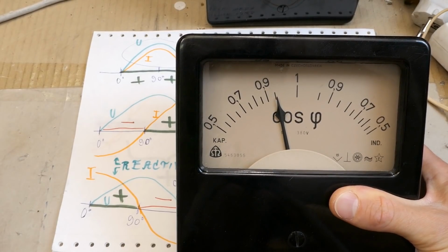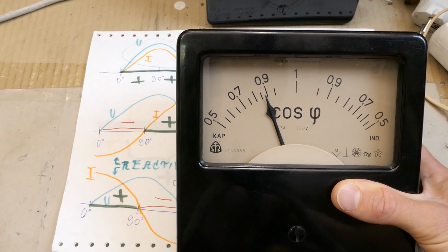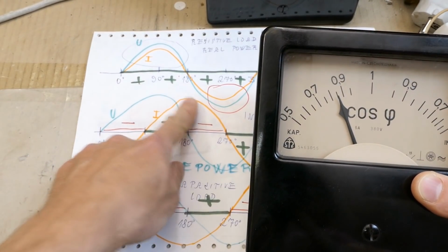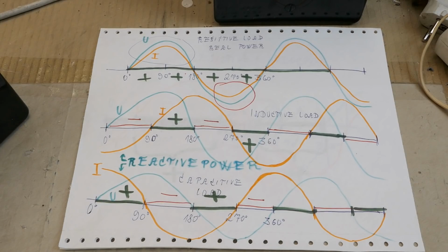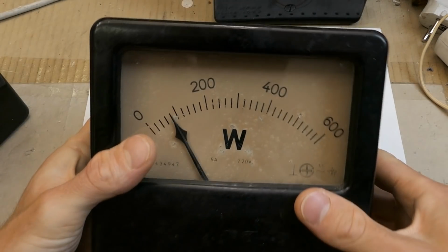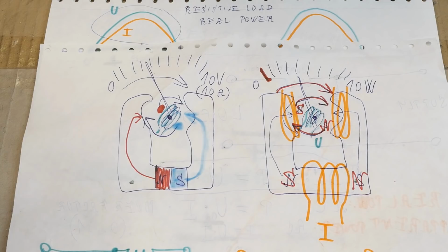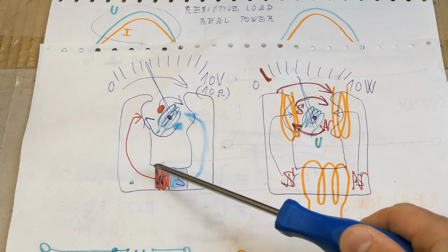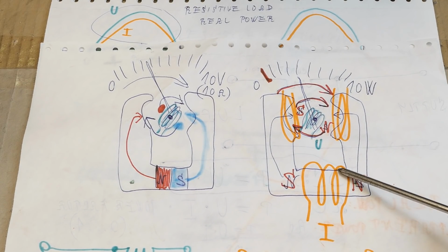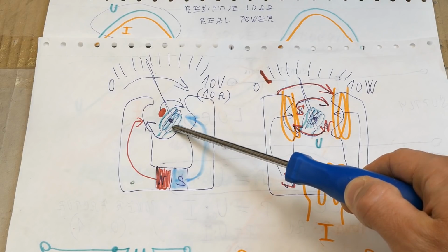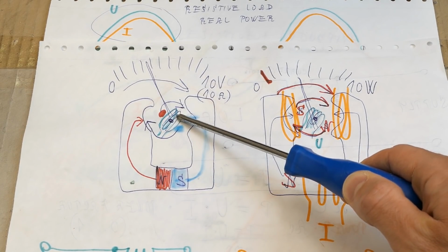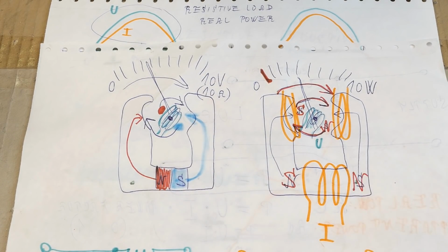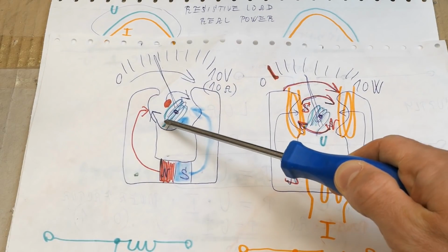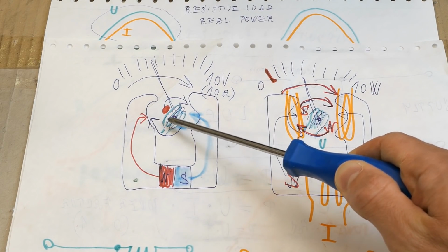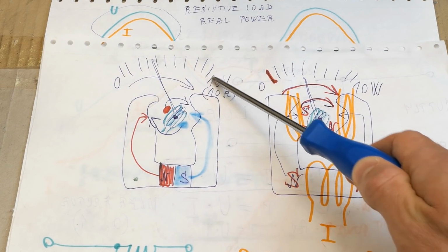But now let's finally get to the power factor meters, and let's see how they measure the power factor. They basically measure the phase shift of the current in reference to the voltage, and the system inside of them is actually even more complex than the system in wattmeters. In the previous video I was showing the system of a voltmeter and a wattmeter. A voltmeter has just one coil, a moving coil or a rotating coil inside of a magnetic field of a permanent magnet. If it's a voltmeter, the coil is connected to the measured voltage, usually via a resistor, and the deflection of the needle depends on the voltage.